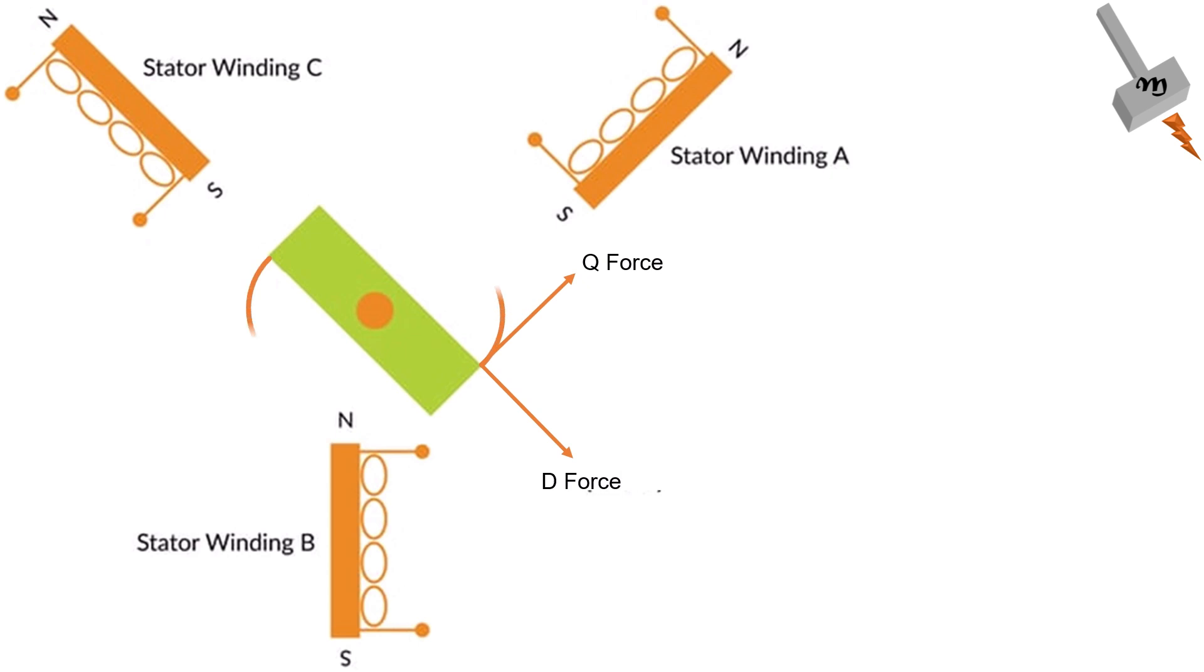These two components are controlled independently, allowing for more accurate and dynamic control of the motor. The D-axis current component represents the magnetizing current, while the Q-axis component represents the current responsible for generating torque. By controlling these components separately, vector control maximizes the torque production and optimizes the motor's performance across a wide range of speeds.